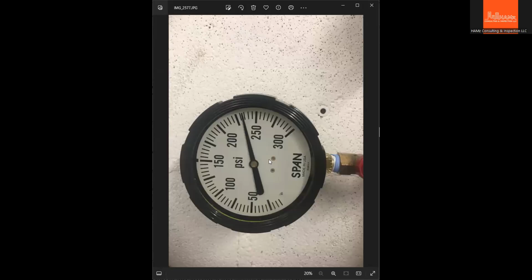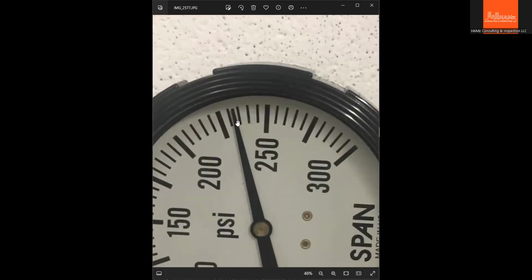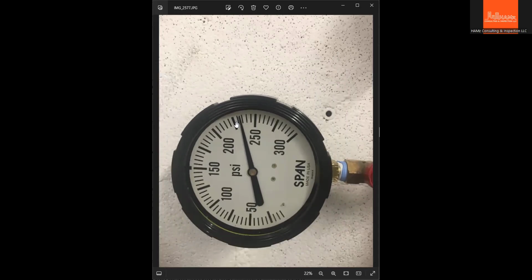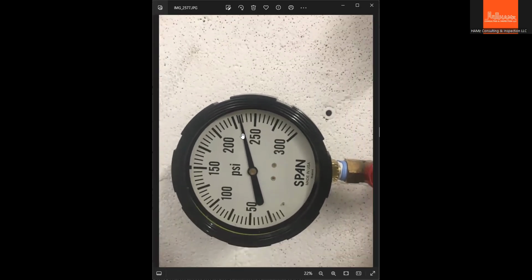Okay, so in this case, I think the pressure drops. Remember, we had between 240 and 245 pressure. Now it was between 230 and 235, so roughly 232 psi right now. So it dropped about 10 psi. So I think on the next photo, we did retest this one for another 2 hours. So they did pump it up.